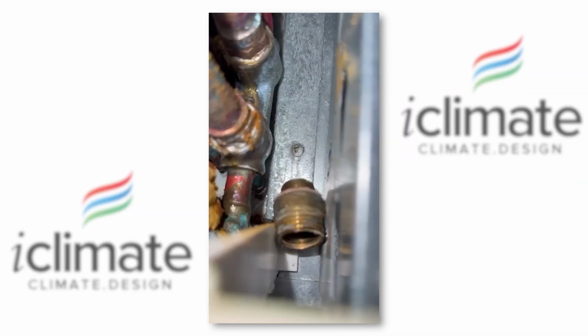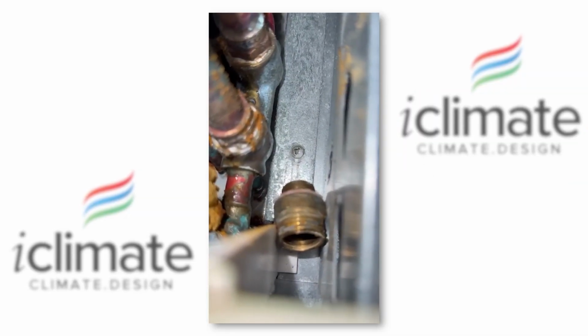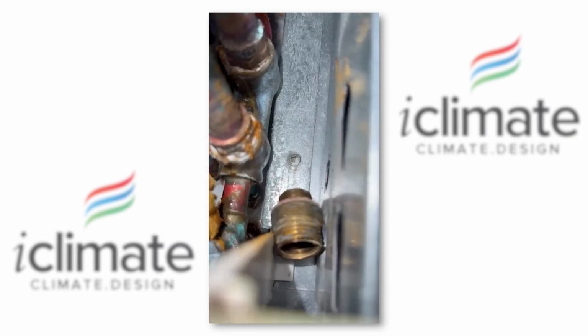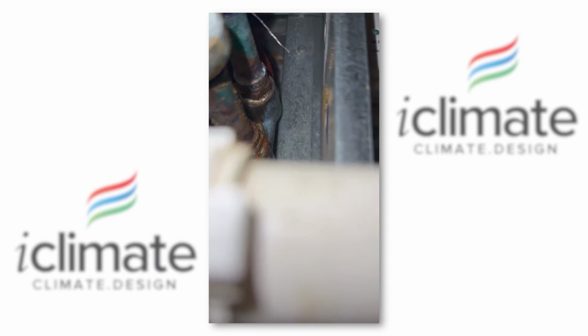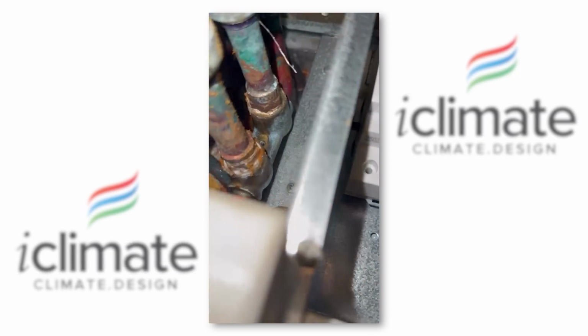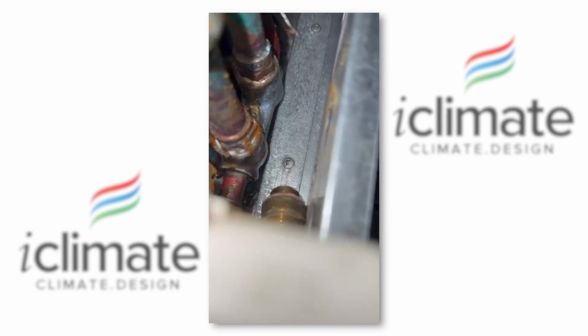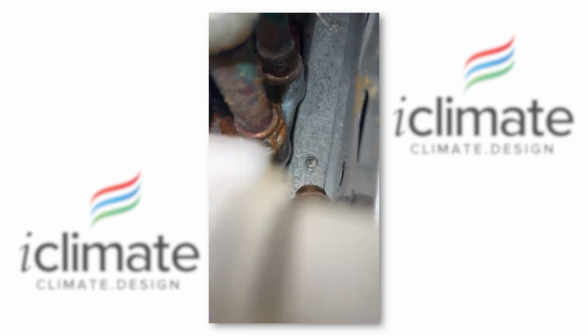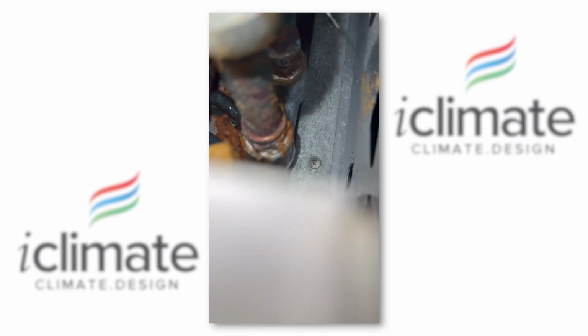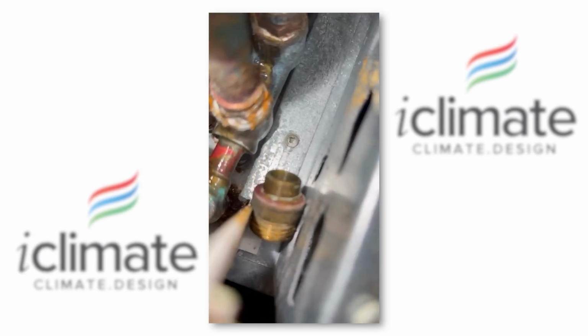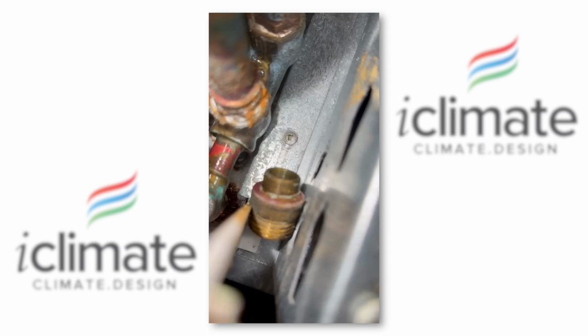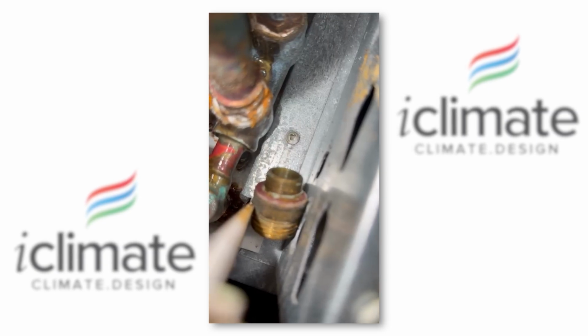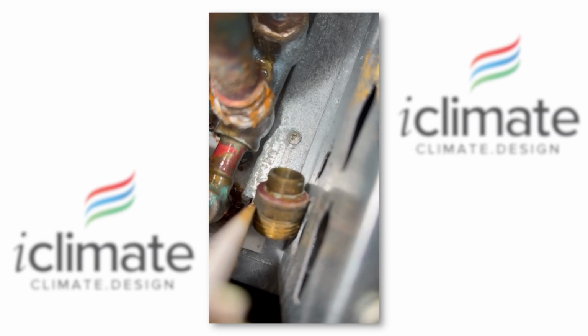Right, you see the drops. There's one there, there's one from this union, but that drop could just be something at the top. That's definitely, they've done something there, yeah? Because can you see there's a fitting stuck in the middle there, loose fitting. So if they've changed the fitting and then it's leaking, it's not from the fitting, it's from the cap, it's from the heat exchanger. Yeah, we can see there's a leak there. It's dripping down the heat exchanger and you can hear it. You can literally hear that leak.